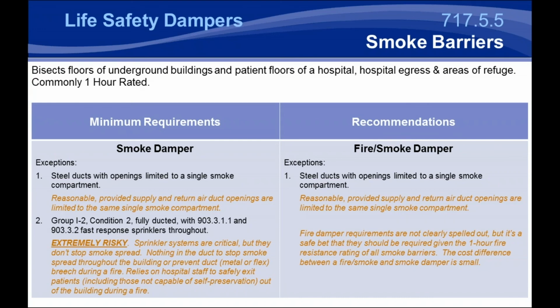Because of that, and because it relies solely on the hospital staff to get the patients who typically can't get out themselves out of the building in time while the sprinklers are extinguishing the fire and creating a heavy smoke load, we recommend that all smoke barriers have a minimum of smoke damper requirements and typically fire smoke damper requirements to make sure that the damper will stay in place if there is a duct drop or a duct penetration type of occurrence, and give the most amount of time for the hospital staff to get everyone out safely.